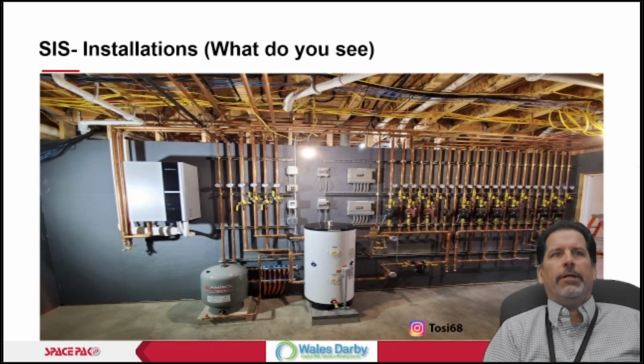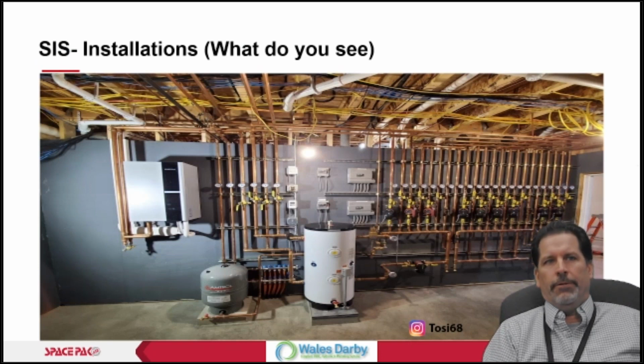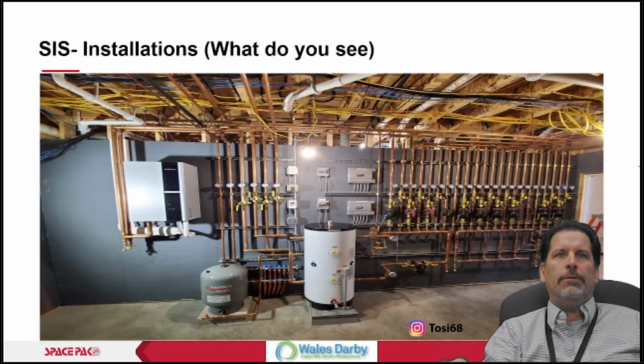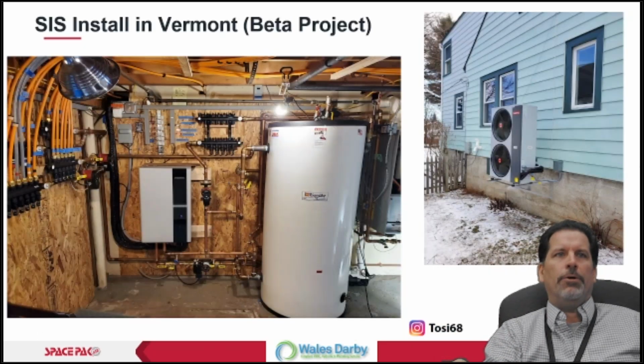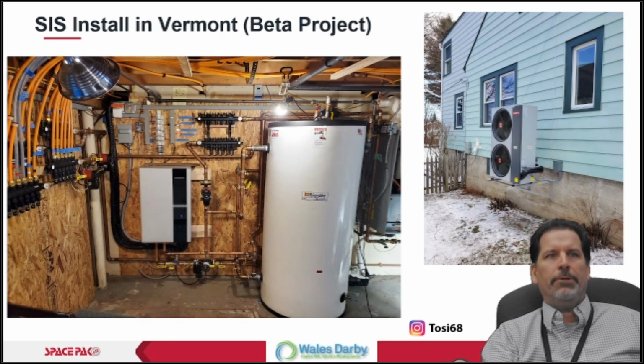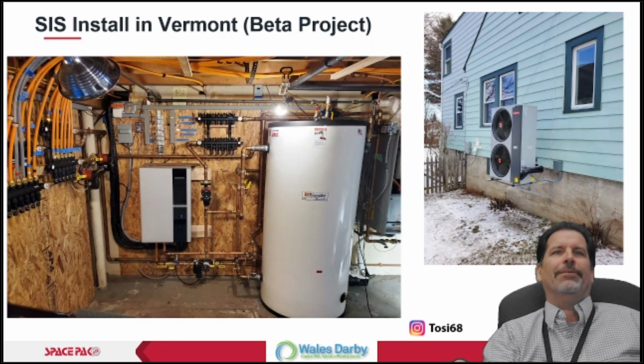It becomes a very comfortable scenario to build out from once we understand what our loads are, right? Great shot here showing you both indoor and outdoor. You do not have to touch the refrigerant. It's sealed, it's done. Once it's in, it's in. Unless you pierce something and you hear a leak, then we'll discuss that. But for the most part, the packaged approach is here now. Like I said earlier, you build every boiler like it's the first boiler ever built. You buy all the components, you have to place them in certain spots, you have to have the space in which to build it and the talent in which to understand it.